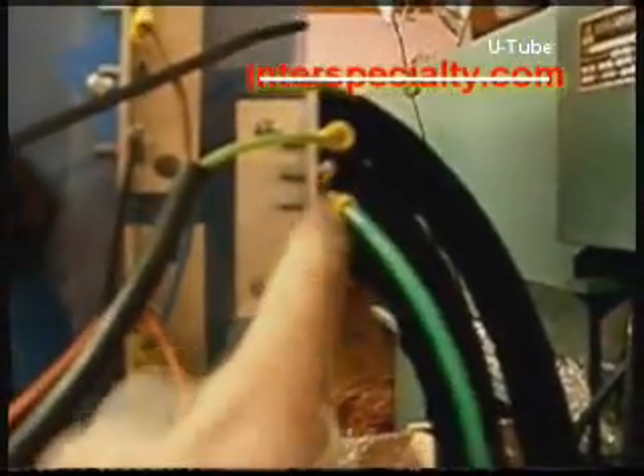The air valve then has one of its wires, being that it's a 110 volt valve, connect to the other normally open contact of the fan relay. Once again, you see the high voltage 110 line there.